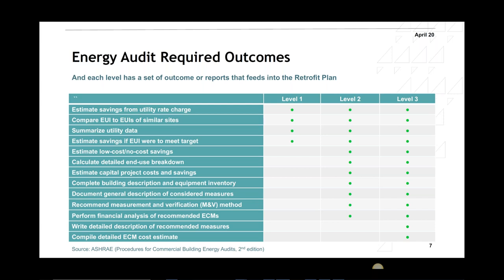For a level two audit, you need to estimate the low cost, no cost savings. So let's say you go and find that the pressurization air handling unit or the outdoor air handling unit is working 24/7, and it's an office building. You don't need to run it 24/7. Maybe during this pandemic it would be a good idea to keep the ventilation, but during normal times, you should be turning off the system when there's no one in the building. So when there are no occupants, you turn off the systems. That is a low cost or basically a no cost measure. You can go to the BMS and change the schedule of that particular equipment, and that will save you a lot of energy. You need to calculate a detailed end use breakdown.